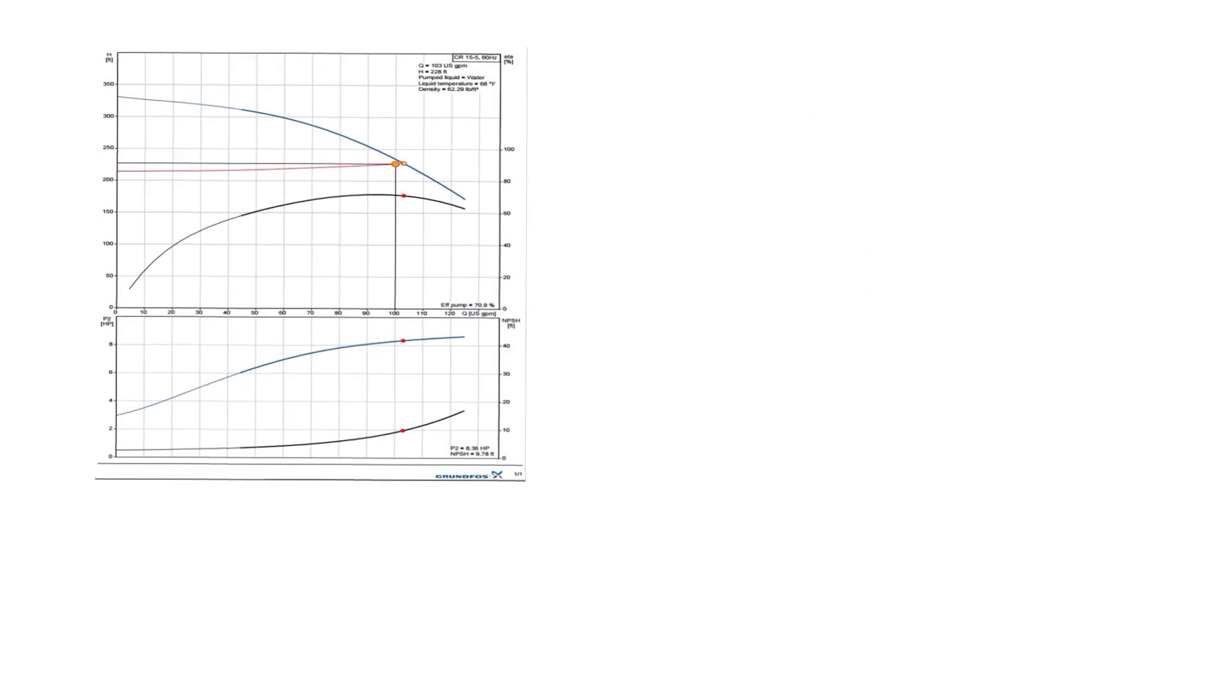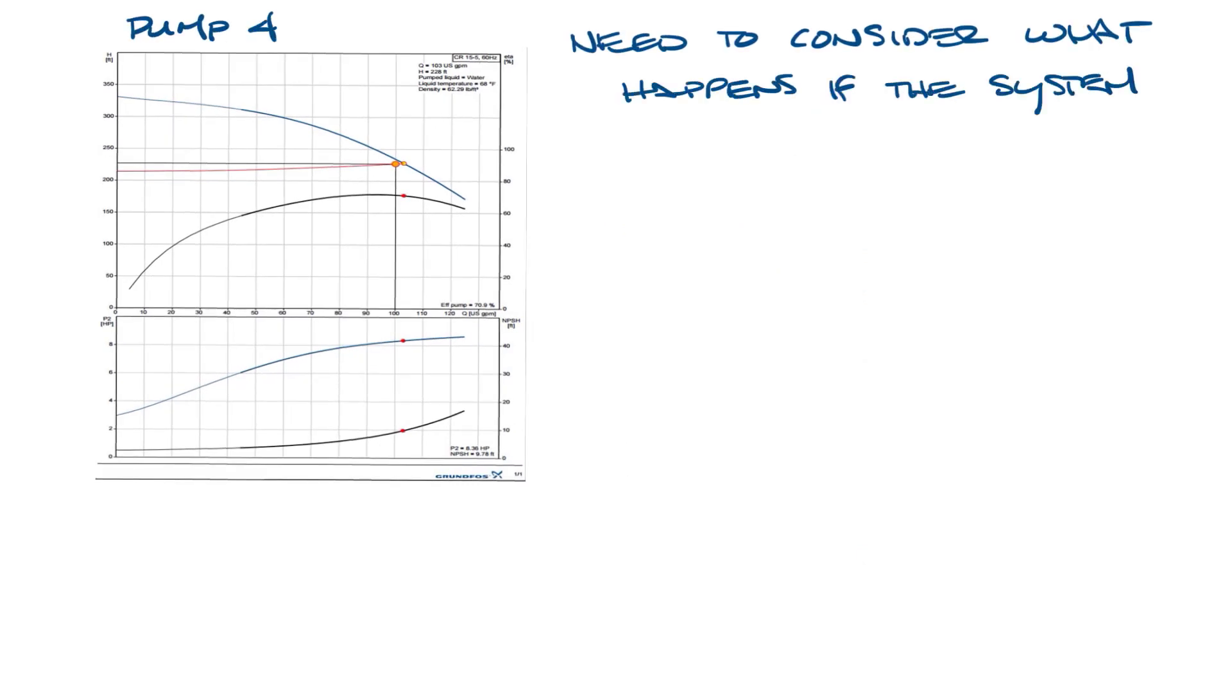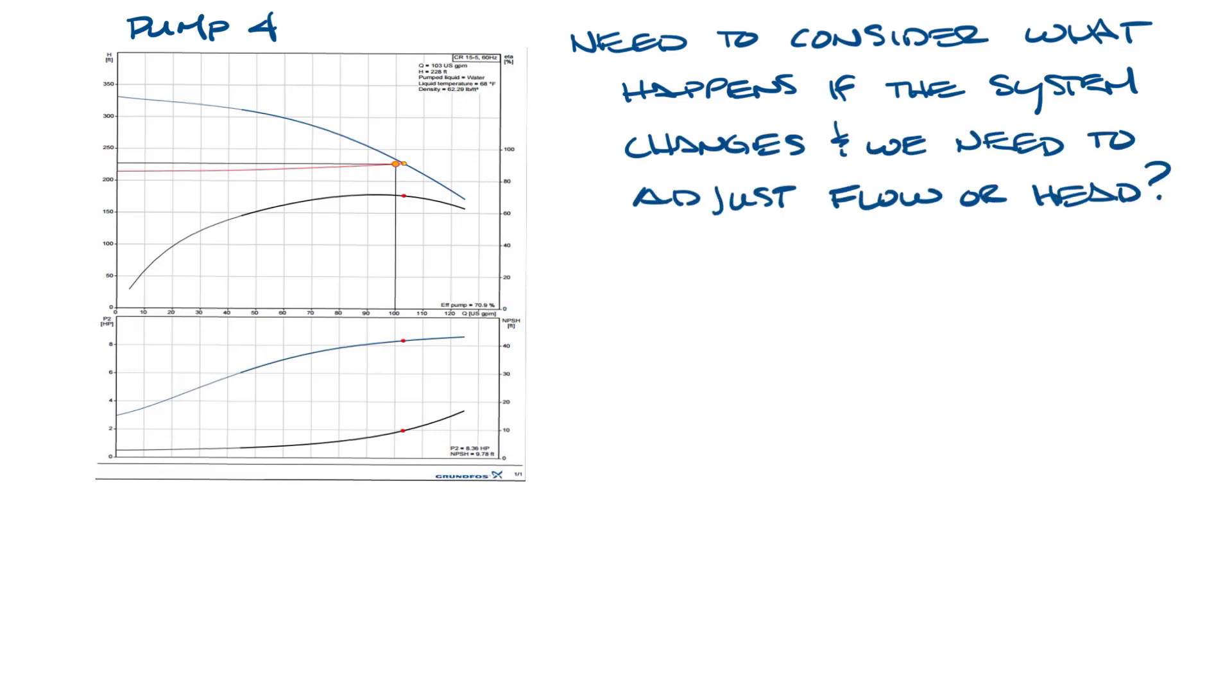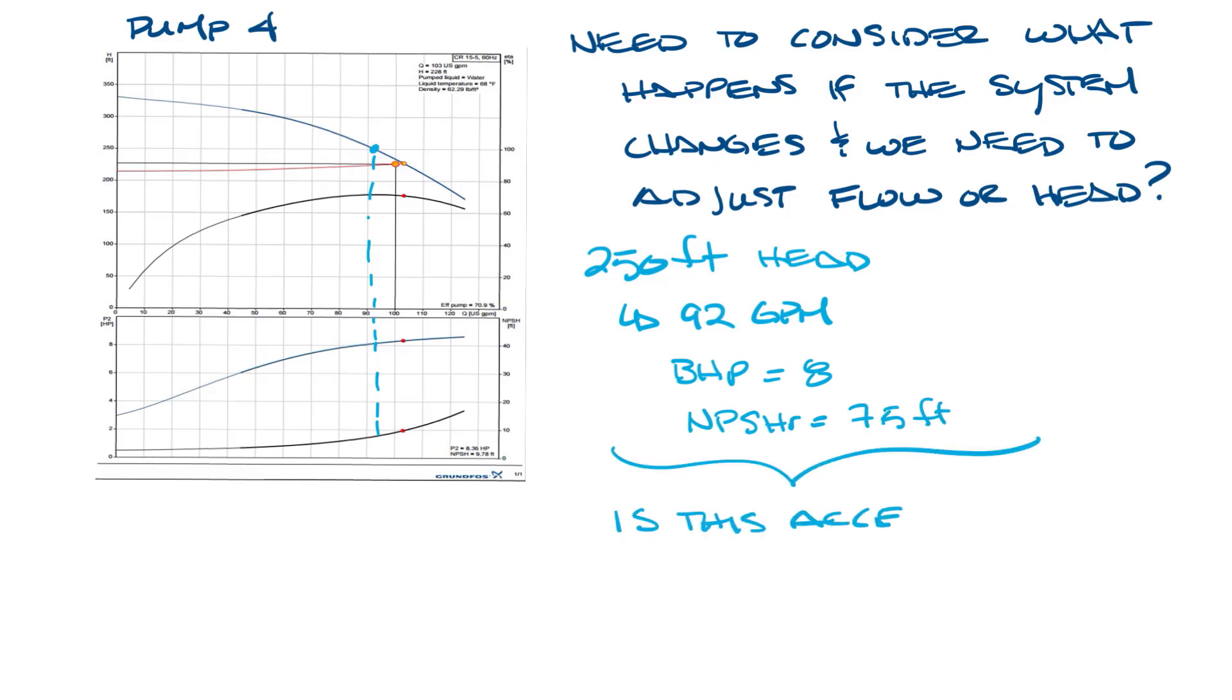This is the curve for pump four. One thing we need to consider here is what happens if our system changes and we need to adjust the flow or the head that the pump produces. Let's say we need 250 feet of head. How does that affect our performance? If you bring your operating point over here to 250 feet, then we follow that down and we'll see we're getting about 92 GPM. Our brake horsepower went to eight, and our NPSHR is now about seven and a half feet.